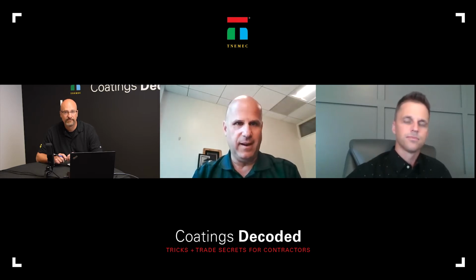Okay. So at least in my mind, when I'm walking through the hardware store and I'm looking at something with an R19 versus something with a greater RValue, the greater RValue is thicker, versus a KValue, which remains constant no matter the thickness. Is that right? Well, if you're looking at the same material, right? If you're walking through the hardware store and it's all fiberglass, then it says R13 or R19, likely the only difference between the two is the thickness, where the thermal conductivity, or K factor, would be identical for those two materials. One is for 4-inch studs and the other is for 6-inch studs. And that's the difference there.